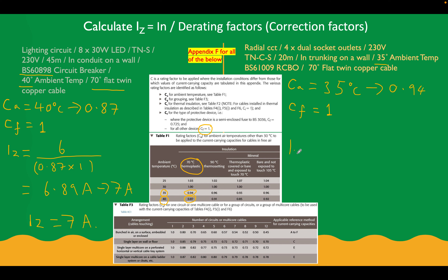Now for the radial circuit: IZ equals our IN of 20 amps divided by our correction factors: 0.94 × 1. That gives us 21.27 amps, which we round to 21 amps. We've now worked out the current carrying capacity of the cables in the installed conditions — the radial circuit cable needs to carry 21 amps, and the lighting circuit cable needs to carry 7 amps. This will help us select our cable in the next stage.